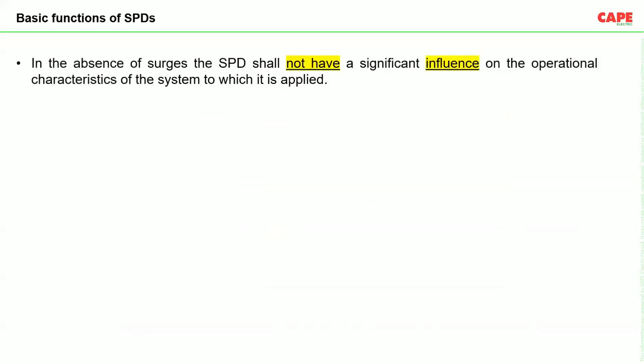So, basic functions of an SPD. SPD has basically three major functions. In the absence of surges, SPD shall not have any significant influence on the operational characteristics of the system to which it is applied. That means once we install SPD inside a system, in case there is no surge, when the voltage is normal and stable, SPD should not create any interference. It should be a completely passive element. It should not interfere in the normal working of a system.